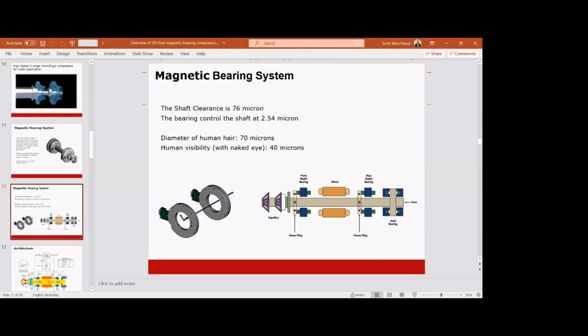And these sensor rings look at the radial positioning of the shaft, and this front sensor ring looks at this target sleeve here at the front, and that goes back and tells the actual bearing how much power we need to put into the actual bearing. And these actual forces can be quite high. So the higher the pressure ratio, the higher the actual forces are on this rear bearing. And that's the limitation on a single-ended compressor.